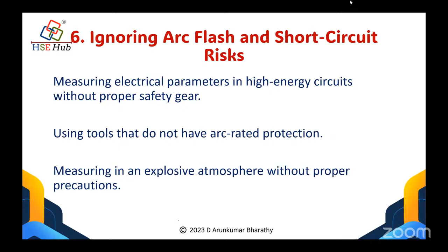There are gloves that look like denim jeans cloth, and they will also have their own arc rating. So in situations like confined spaces and heavy furnaces, we have to use arc protection systems to avoid the risk of arc flash. See, once it happens, it will be like a blast. And in explosive atmospheres, zone 1 and 2 areas, without proper precautions, we are not supposed to measure. So the environment also has to be considered: where we are working, what is the risk in the environment, whether it is a hazardous area or has flash risk. Without this understanding, one should not go for a measurement.